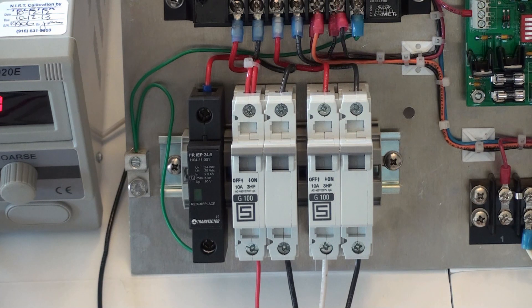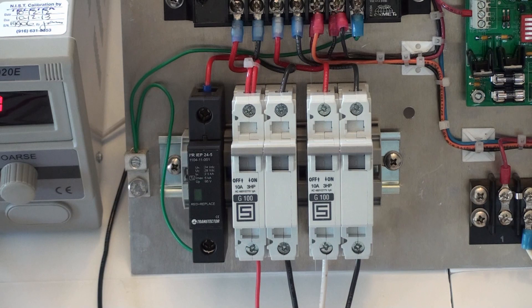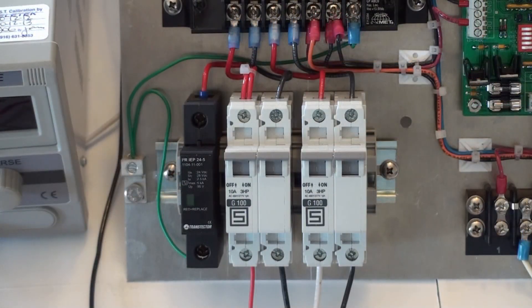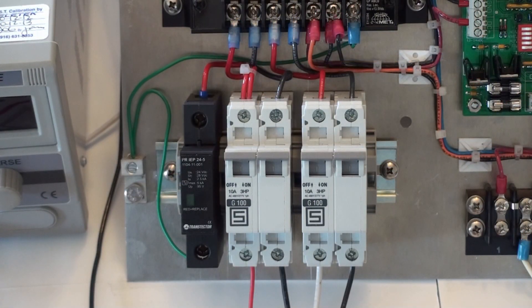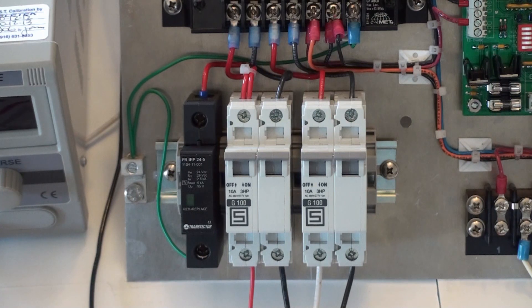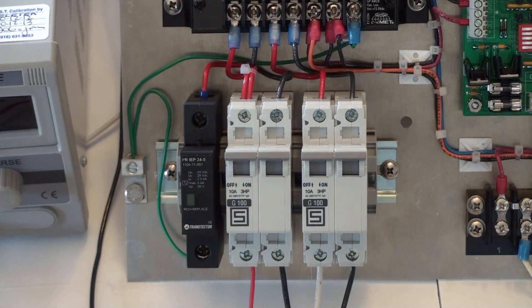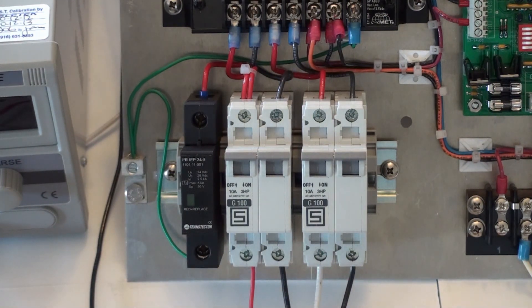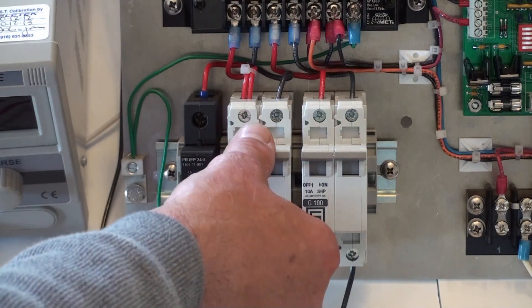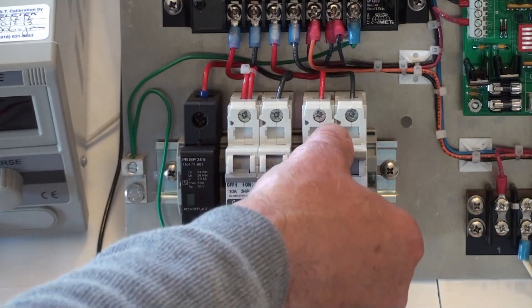In this case, remove the module from the base and replace it. To replace the module in the surge suppression device, first begin by switching off all power to the system. Begin with the solar panel and then the battery.